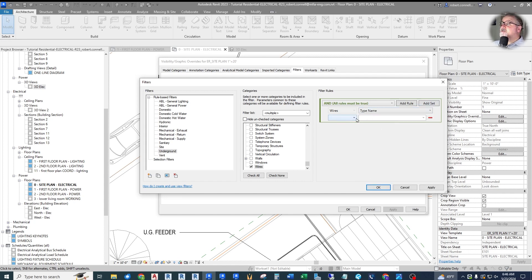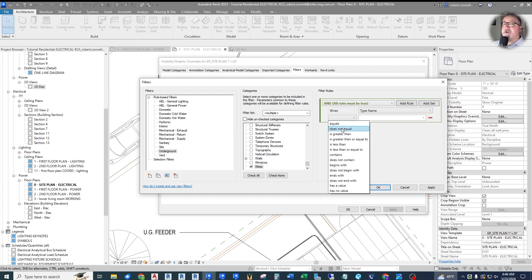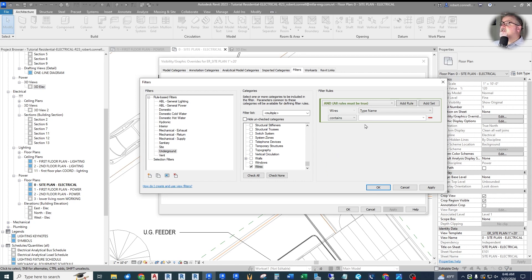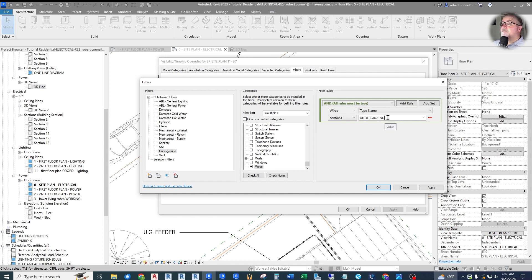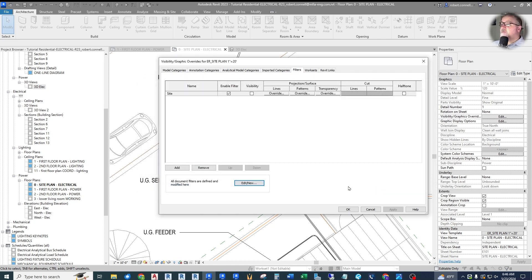Now what do I want to look at in the wires category? I'm going to look at the type name. I call it underground. Type name. Now here's the rule. If it equals, not equal, is greater than - you can use all kinds of logic. I'm going to say either equals or I'm going to say contains. Let's just say contains to make it more versatile. Underground. Now if it contains underground, then it meets the rules of this filter.